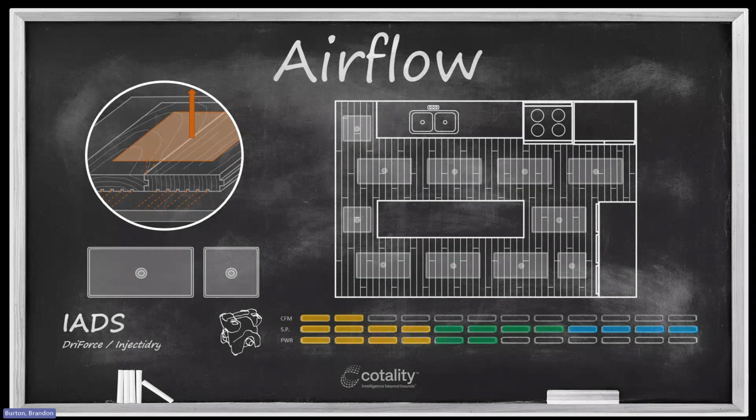Now, the last point I want to make on this slide before we move off of it is one other advantage in how to install these, which is understanding how to plumb these different mats together. Your inter-air drying system, if you're using a DriForce specifically, somewhere in the neighborhood of about 5-6 mats is about the most I would run off of that blower.